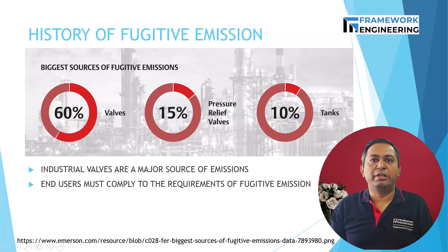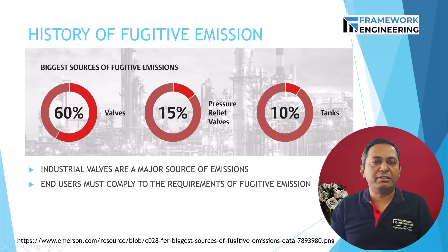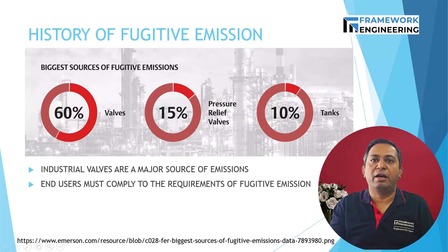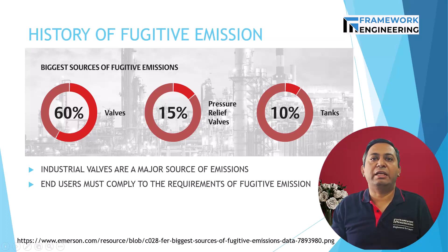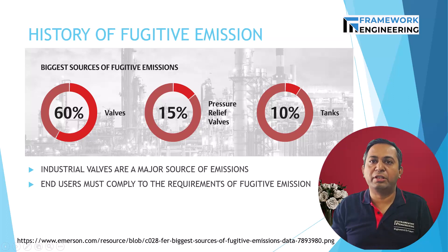With emissions, the end product may differ and energy is lost — meaning the end user in any case loses money if it is not able to comply with the requirement. In chemical plants, the valves are responsible for around 60 percent of fugitive emissions, making them the most significant source of emission. However, generally only one or two percent of valves in any facility are actually leaking.